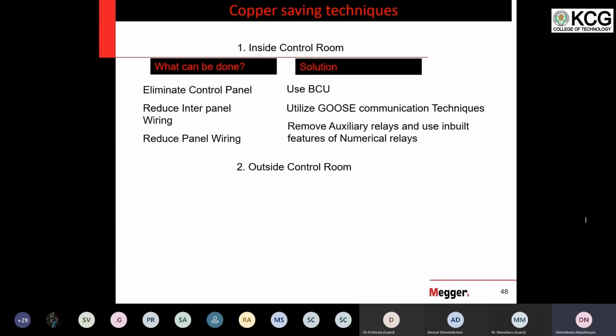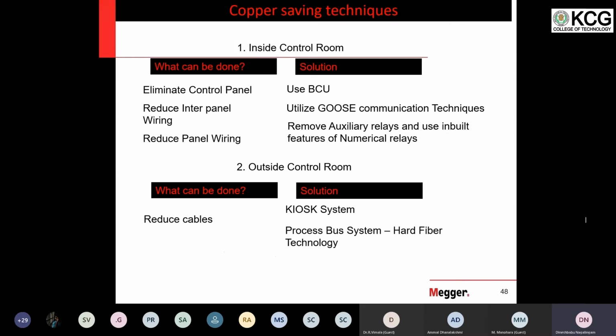Moving on, outside the control room, what can we do? Reduce cable. That is the only thing that we can do currently. We cannot eliminate the transformer, we cannot eliminate CT and PT, etc. So currently we can only reduce the cable or eliminate cable to a certain extent. Solution: kiosk system, process bus system. So these are the two solutions that we have. Let us see them one by one.